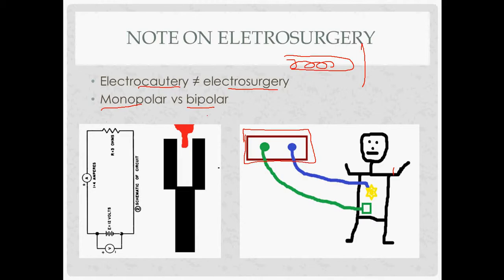For bipolar electrosurgery, the electricity doesn't pass through the patient to a grounding pad. Instead, it passes from one pole to the other through the tissue — just like a typical electrical circuit. The electrosurgical unit generates the voltage, electricity goes from one pole to the other through the resistance of the tissue being cut or coagulated, and returns to the unit all within the tool itself. The electricity shouldn't actually be passing through the patient. So when using bipolar, you can use conducting distension media.